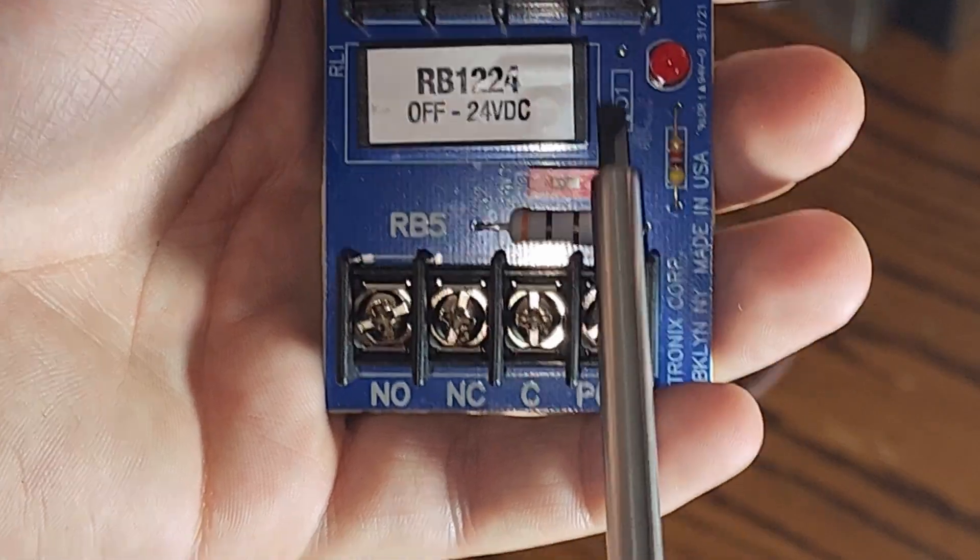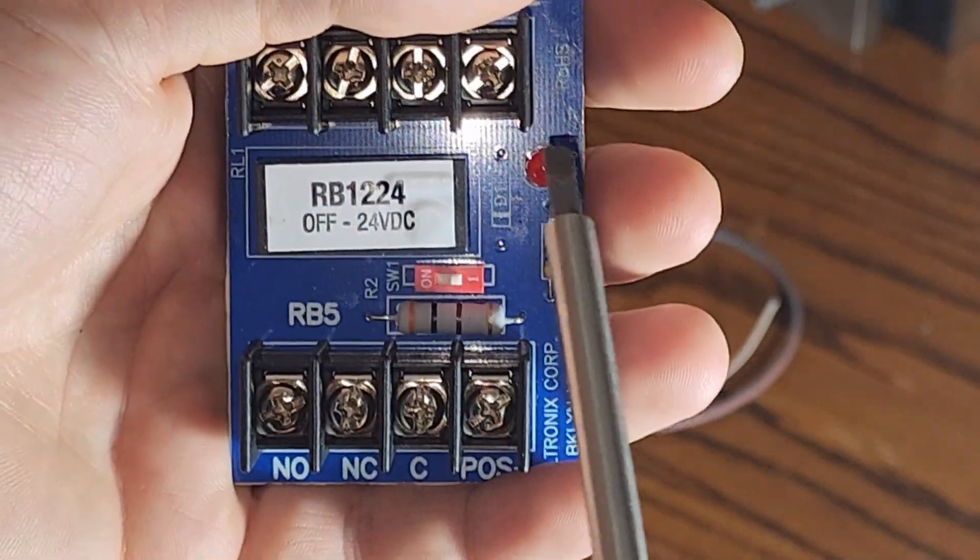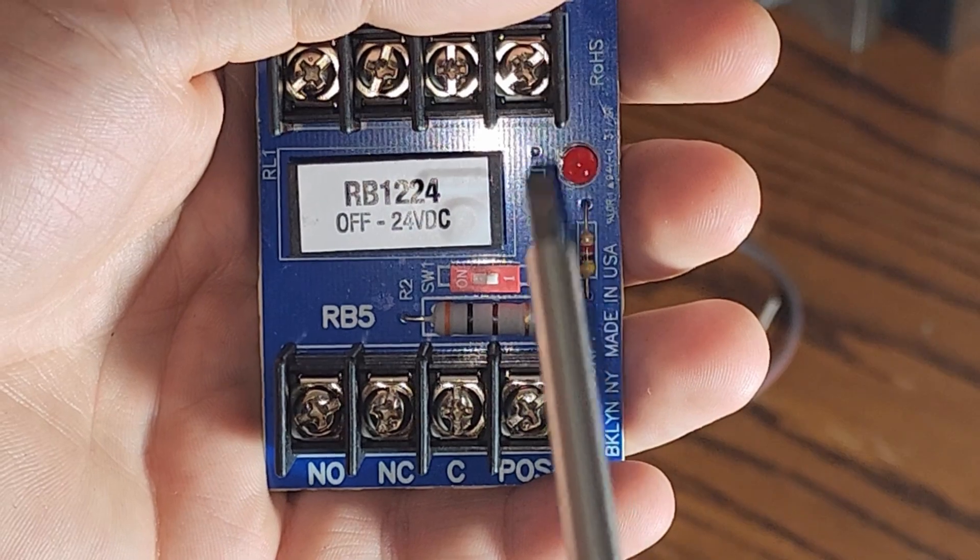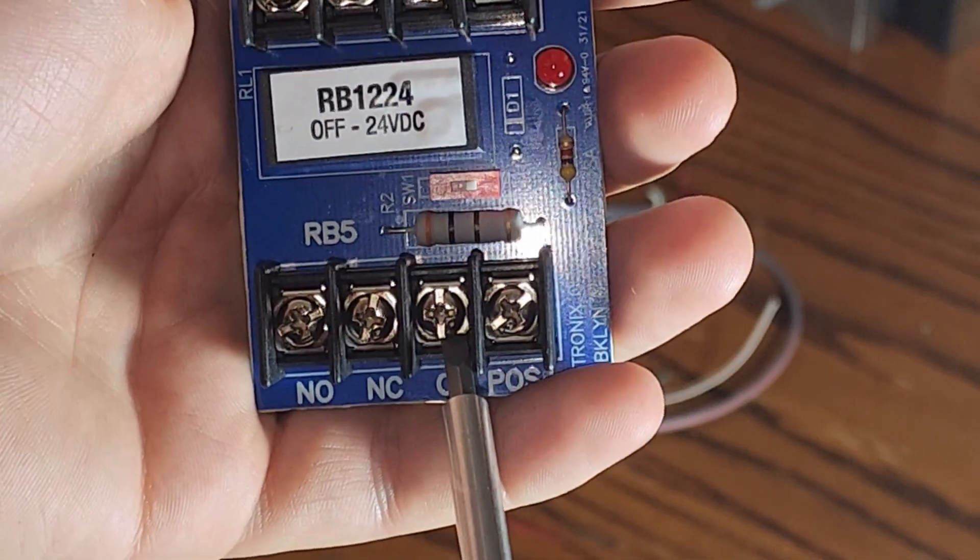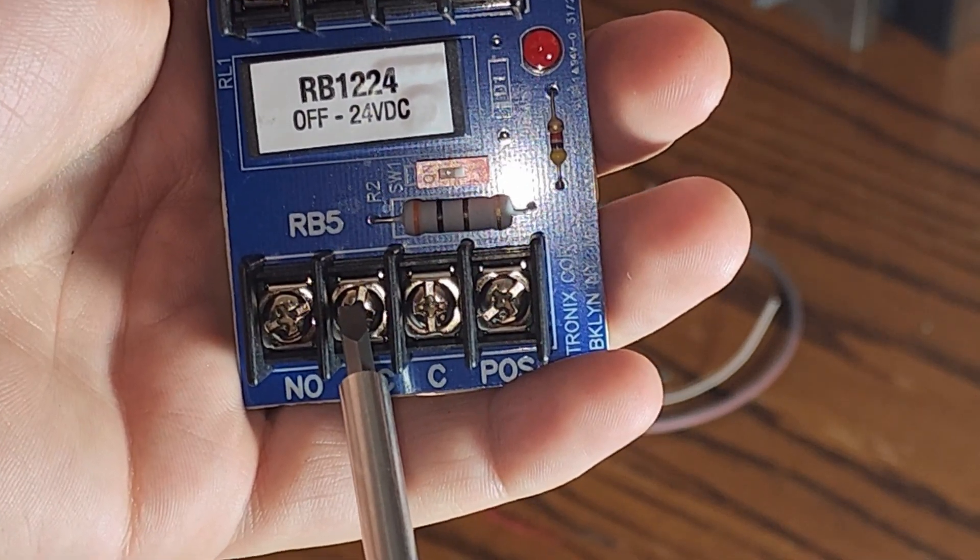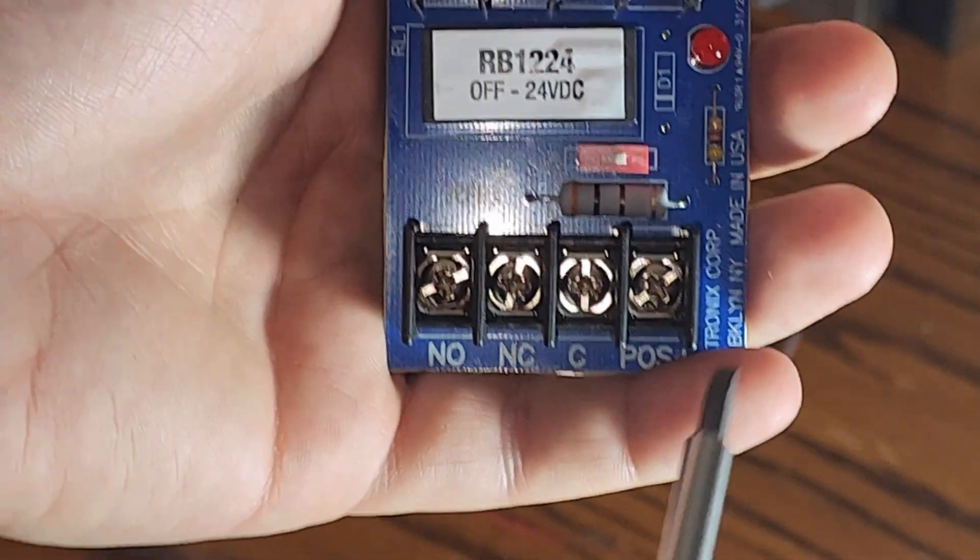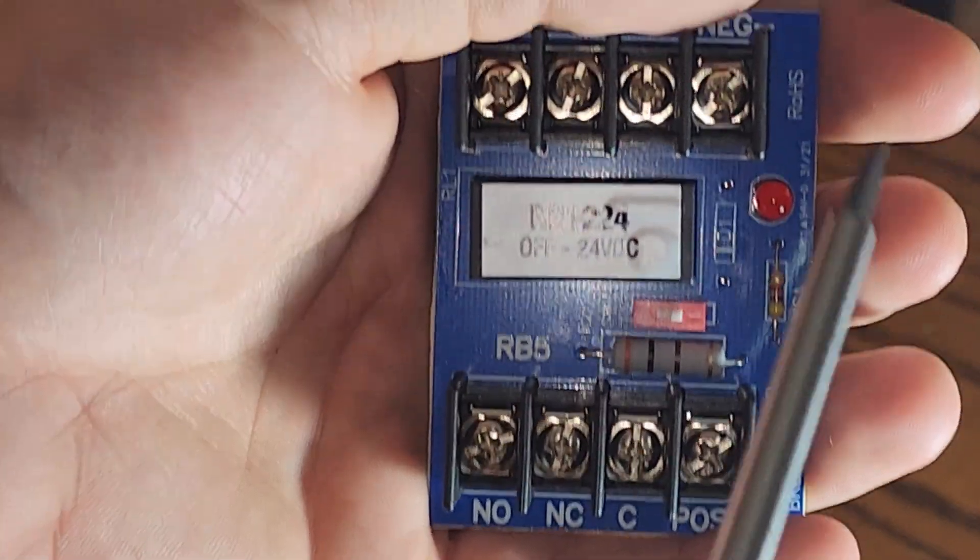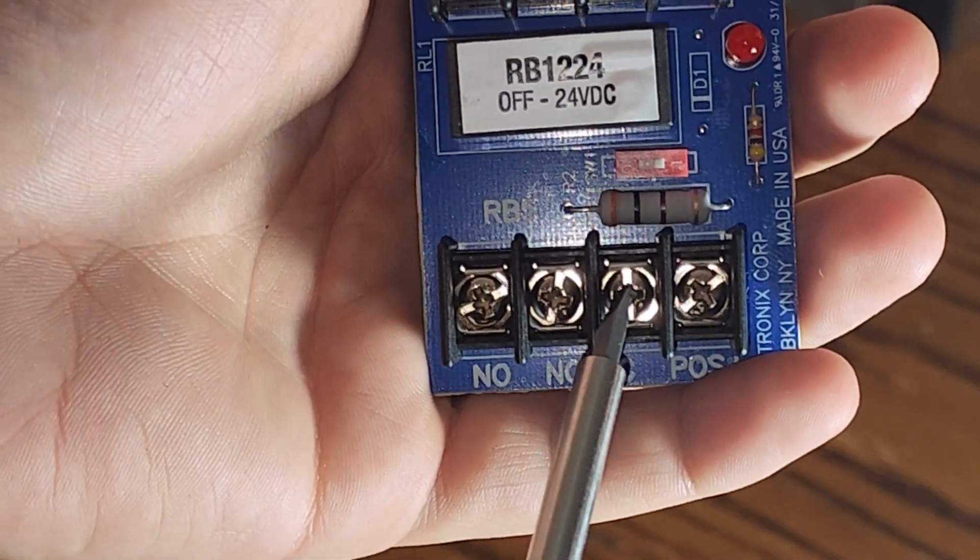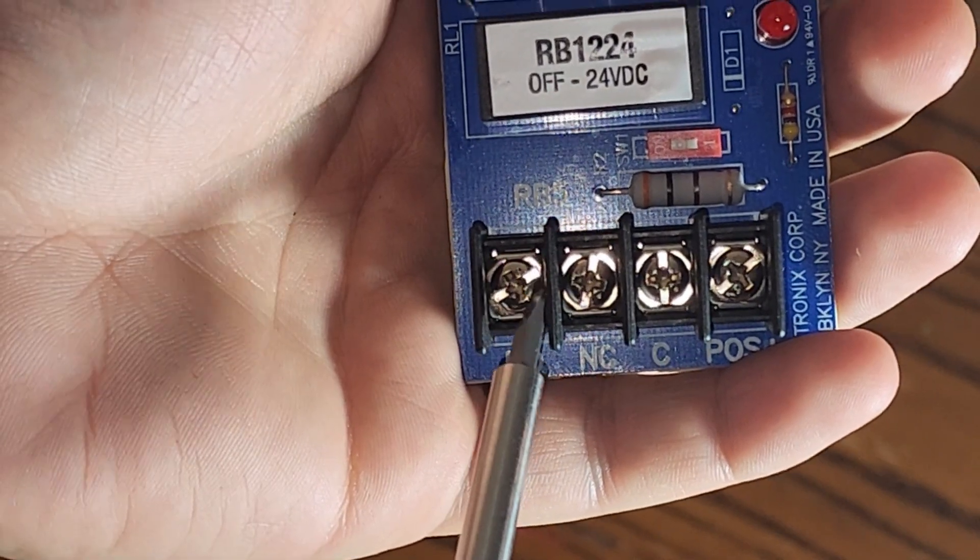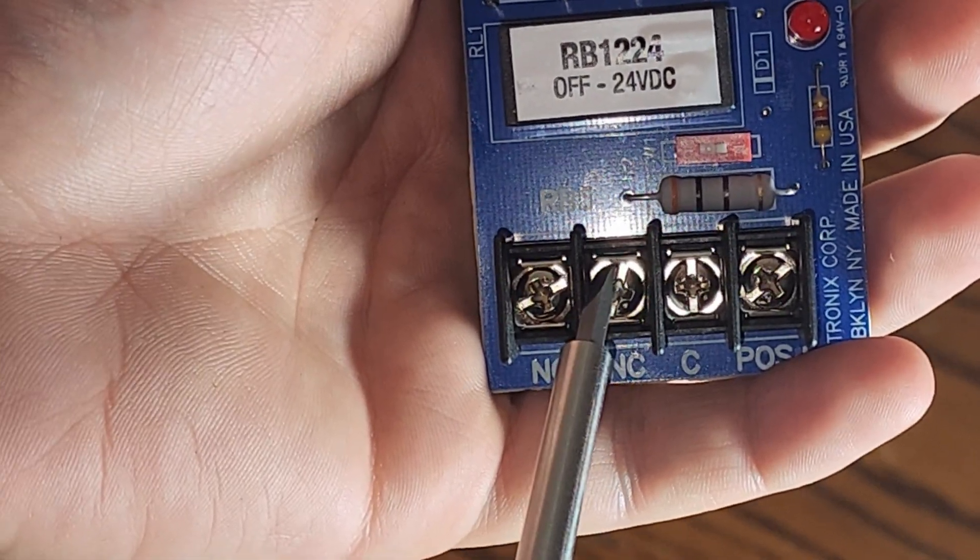In this case, with an RB1224, when the relay is not energized, meaning it is not powered, you're not sending any power here, the common is electrically shorted to the normally closed. If you apply power to the relay with the positive and negative leads, the common then shorts electrically to the normally open, and it breaks its connection to the normally closed.